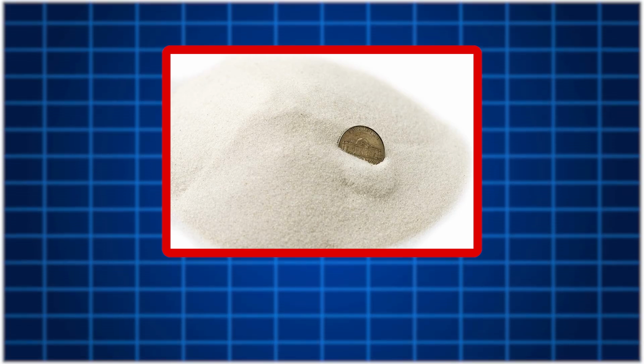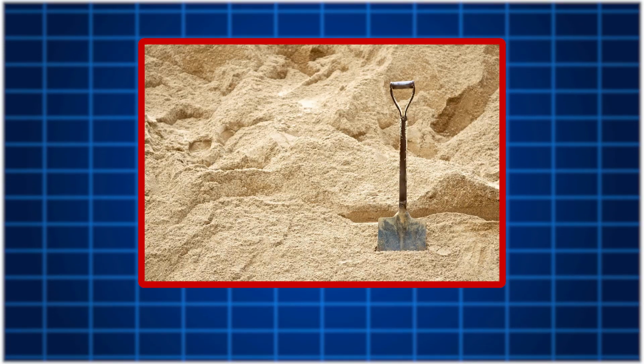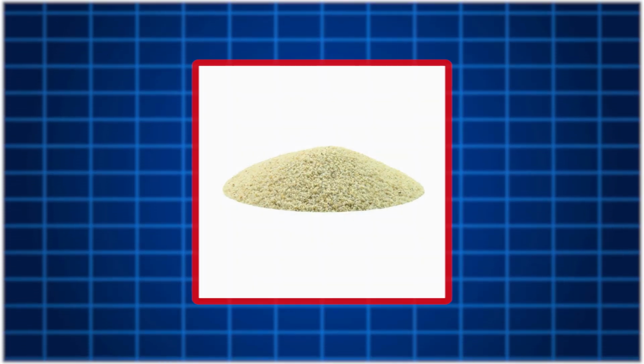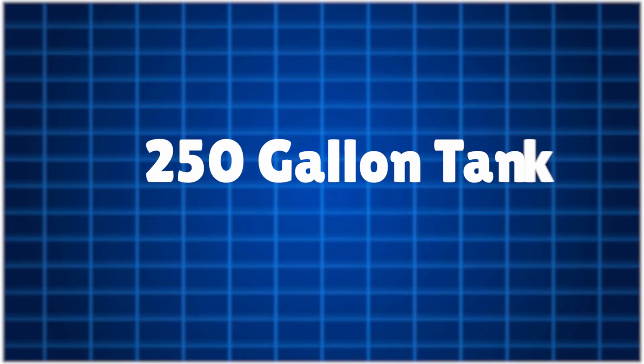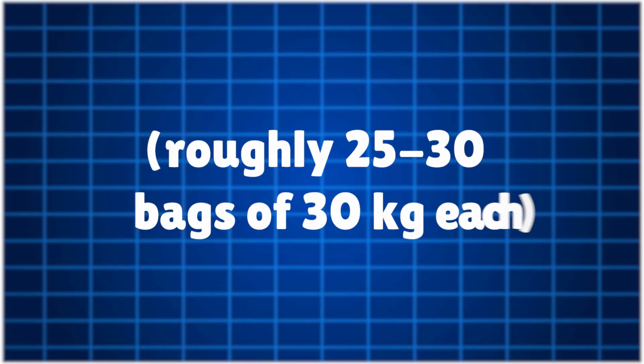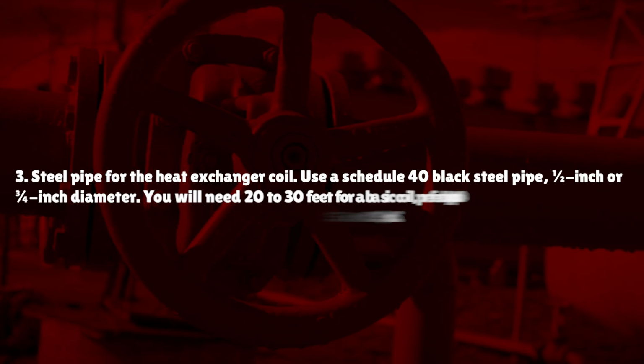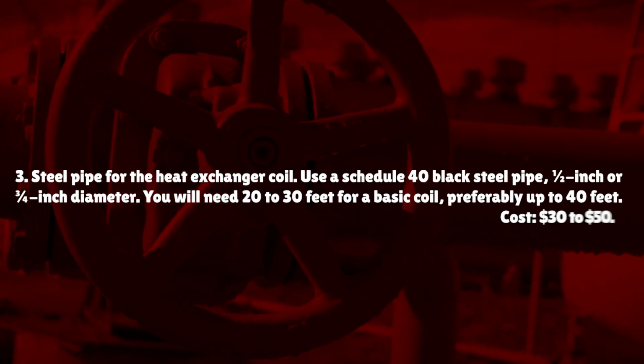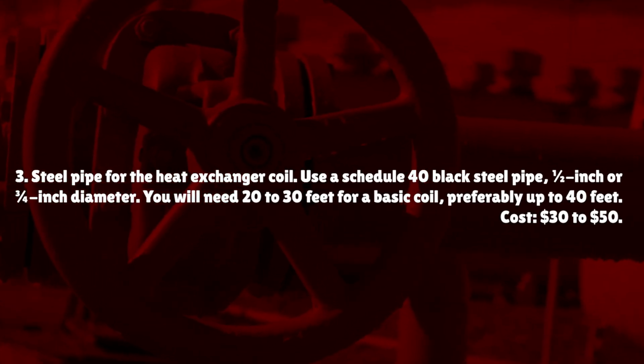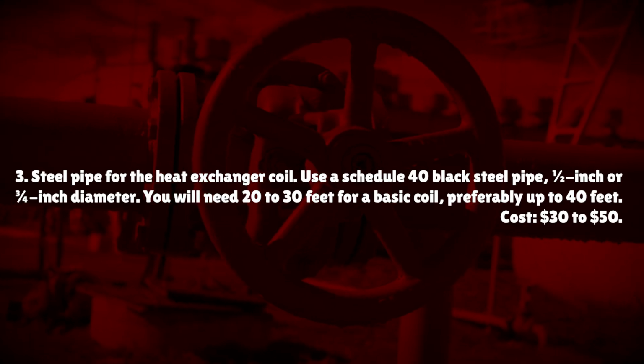Dry, fine-grained silica sand. Avoid construction sand with moisture or beach sand with salt. Use kiln-dried silica sand. For a 250-gallon tank, plan for 800 to 900 kilograms, roughly 25 to 30 bags of 30 kilograms each. Cost $40 to $70. Steel pipe for the heat exchanger coil. Use a schedule 40 black steel pipe, 1/2 inch or 3/4 inch diameter. You will need 20 to 30 feet for a basic coil, preferably up to 40 feet.